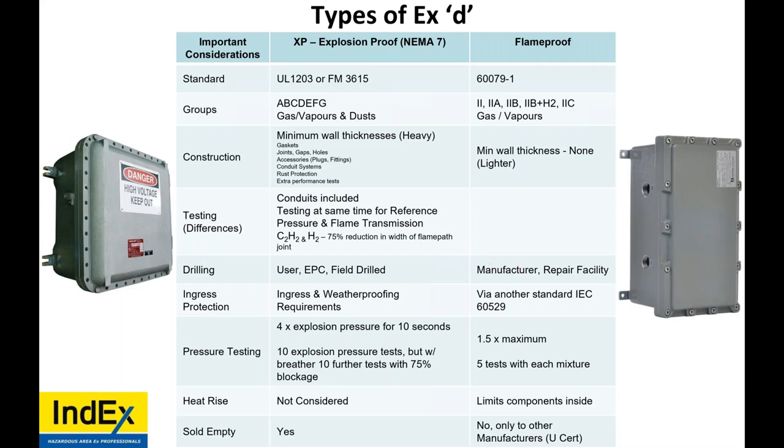Drilling for flameproof can only be done by the manufacturer or a repair facility, an approved repair facility approved by the IECEx certification scheme, or the manufacturer's approved repair facility. For explosion proof, I can drill it as the contractor, I can drill it as the end user, and I can drill it in the field. But for flameproof, it can be NPT and metric threaded entry. Explosion proof can only be NPT.